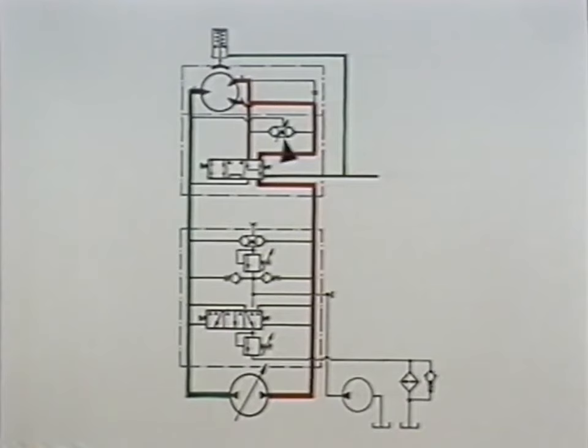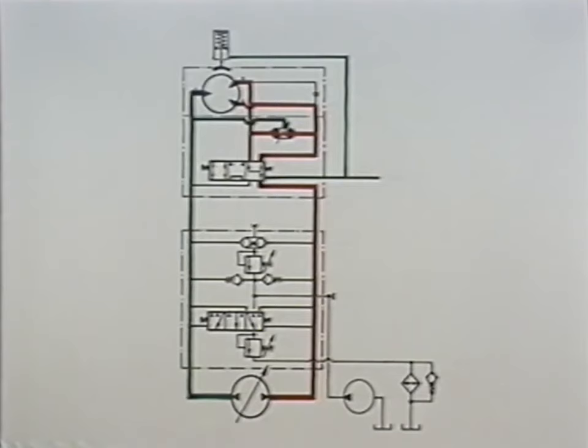The shock absorber valve. Pressure peaks in the circuit are taken care of by a shock absorber valve that forms part of the motor valve, and which discharges a certain amount of high pressure oil to the low pressure side. This valve functions both in the normal, that is the low speed range, and in the high speed range.